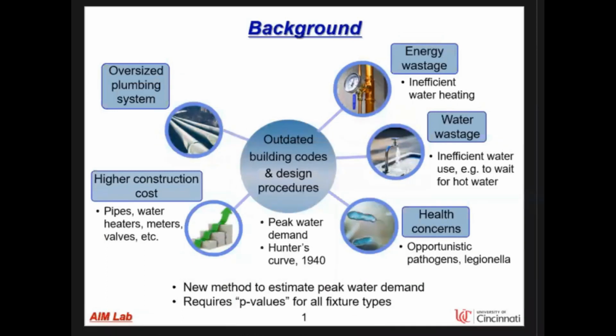The traditional method for estimation, called the Hunter's curve, was developed in 1940 and has become outdated with broad adoption of water-efficient fixtures. This leads to significantly overestimated peak water demand and thus oversized water plumbing systems in both residential and commercial buildings. Oversized plumbing systems can trigger potential problems such as higher construction cost, wasted energy and water from inefficient water heating, as well as public health concerns on opportunistic pathogens like Legionella.